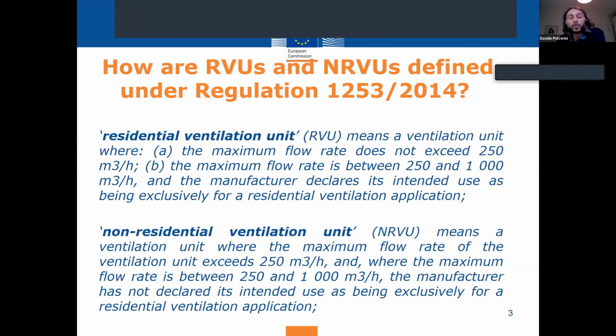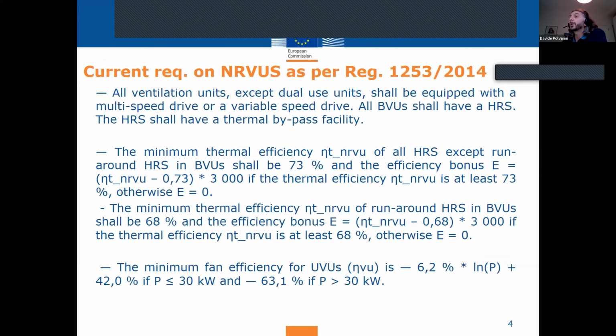I understand today the interest is more on the non-residential ventilation units. And as I told you, we have already an eco-design regulation in place. For the NRVUs, we have a set of requirements, which are compulsorily to be respected by all units. So all ventilation units placed on the European Union market shall be compliant with the requirements laid down in the regulation. Very briefly, all ventilation units, except some exceptions, shall have a heat recovery system.